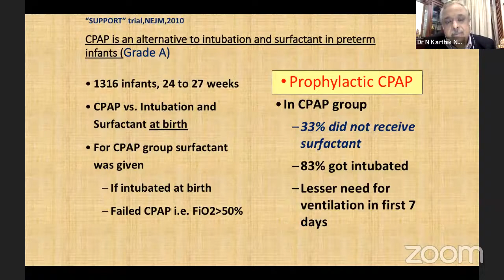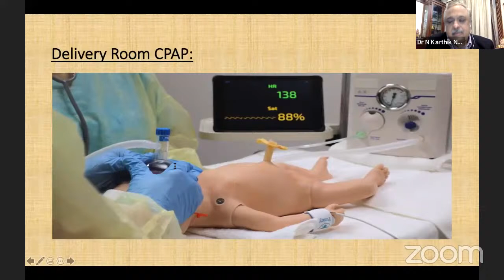Basically, these T-piece devices, as you can see, are able to deliver a fixed, correct pressure, whatever you set. It will not go above the set pressure which you have chosen. So no doubt it can deliver the set pressure of CPAP, or the PEEP, as you have said. It can also help you deliver a blended air and oxygen mixture to the baby. You can have a pulse oximeter with a probe on the right hand or wrist of the baby, delivering the appropriate targeted oxygen saturation. And as you can see here, the CPAP well applied on the nose and mouth of the baby is able to deliver good respiratory support so that oxygenation can improve.